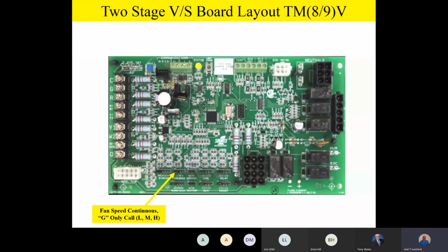Speed: high, medium, low on this particular control board. If you have a G only call on the board, in other words, the homeowner goes to the thermostat sub-base assembly and switches the fan from auto to on, how fast does it run? Well, this is that jumper right there: fan speed, high, medium, low.